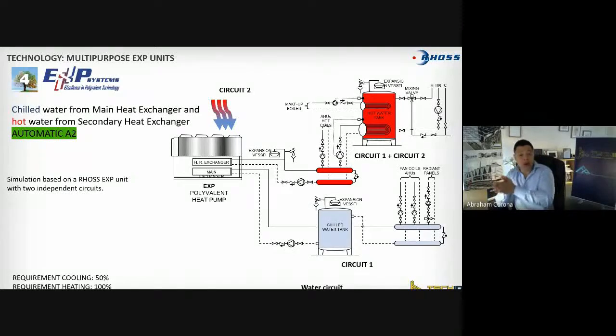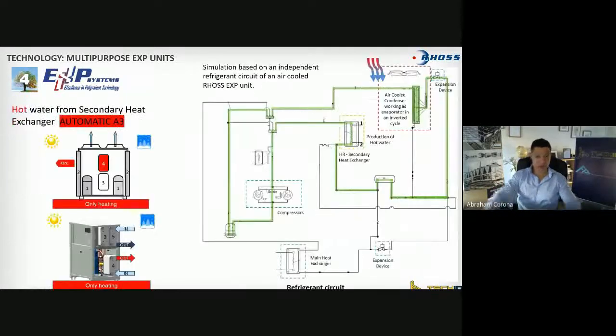So where do I get the other 50%? The controller says, look, I'm missing heating. So the controller by itself is reversing the cycle that I was playing on the next slide of the other circuit. So one circuit will be running as a chiller, the other circuit will be running as a heat pump. It's taking heat out of the environment and it's actually sending this to the hot water tank.